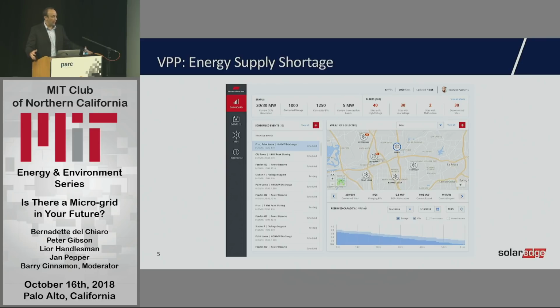We use aggregation of systems to stabilize frequency on the grid. It's a very tricky thing for a network operator to stabilize frequency. As load is reduced on the grid, the generators start to spin faster, so the frequency goes up, and as load increases, the generators slow down. So stabilizing frequency is a big deal - we have VPPs that react to grid frequency and give more power or take more power in order to help stabilize the grid.